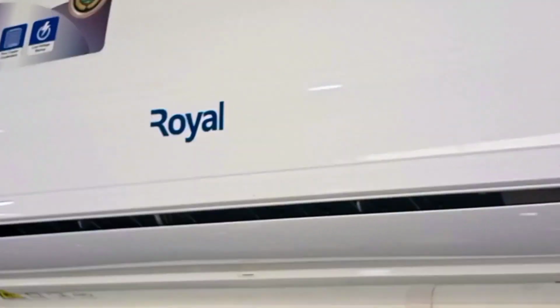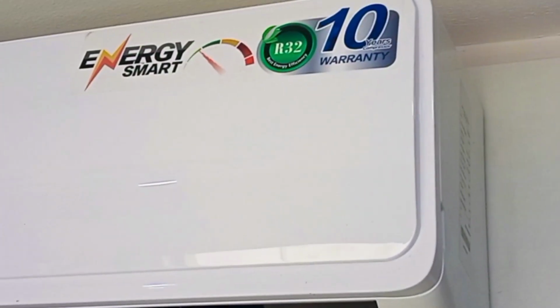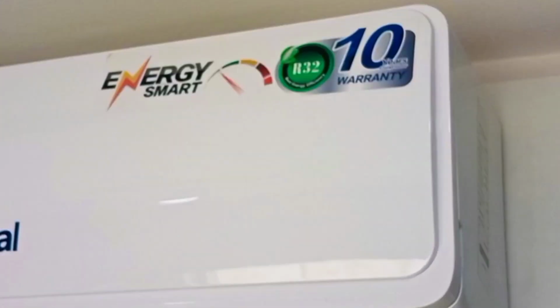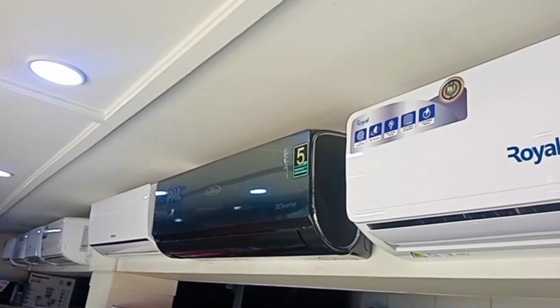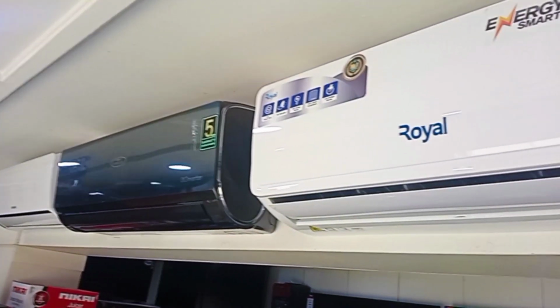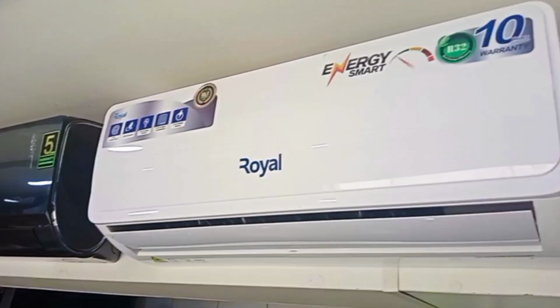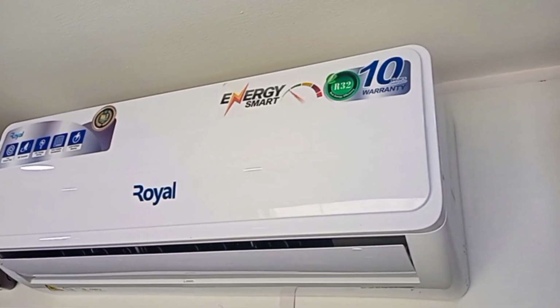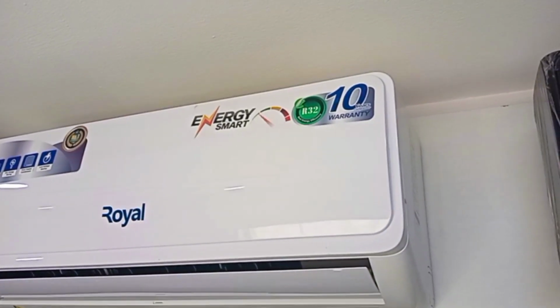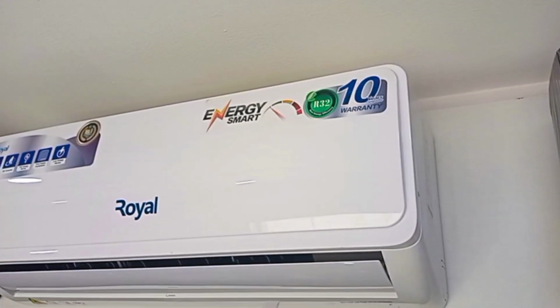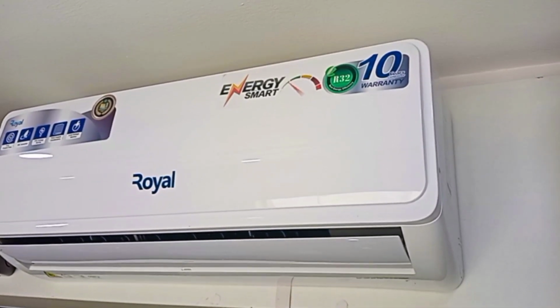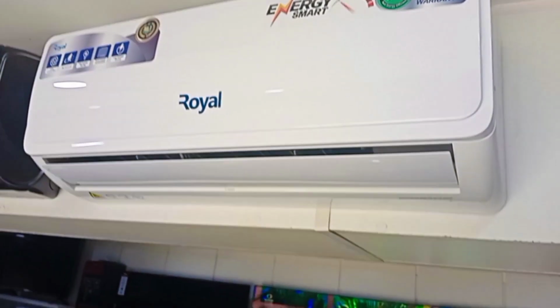In summary, R32 is a low GWP, energy efficient refrigerant that is considered to be a safer alternative to R22 and R410. The choice of refrigerant will depend on various factors such as efficiency, safety, cost and environmental impact, and should be considered on a case-by-case basis.